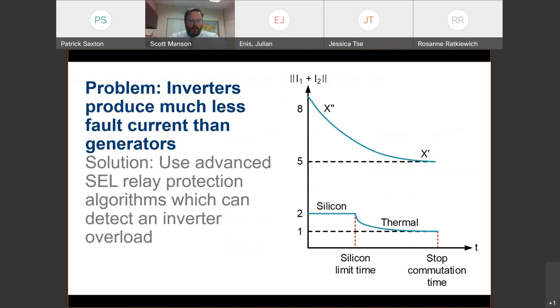So there's always going to be a thermal management system, meaning a block of aluminum, typically with an air-cooled or water-cooled jacket, to extract the heat. And this basic phenomenon that you have to extract the heat from a silicon device forces you to limit the current if you wish to stay competitive. If an inverter manufacturer wishes to sell inverters, they need to go to least cost, which means least aluminum, least thermal capacity. This is the fundamental problem that's driving the protection challenge.